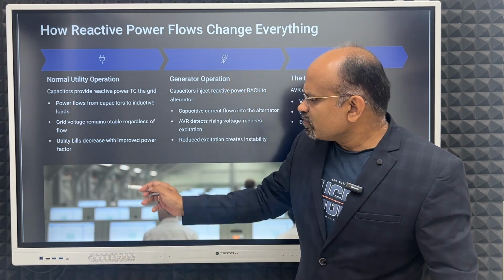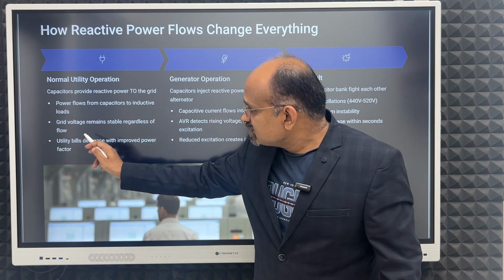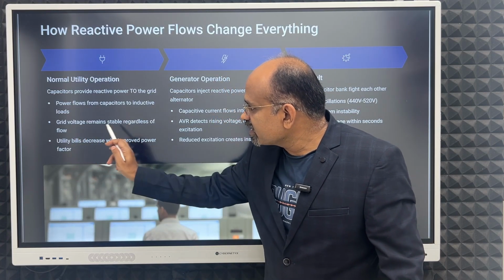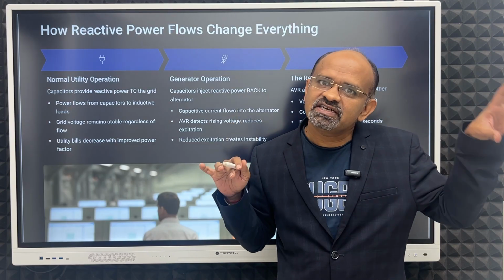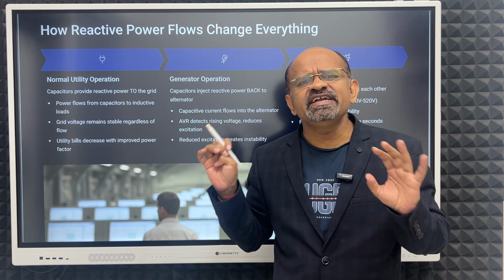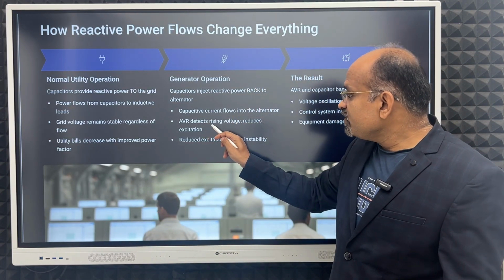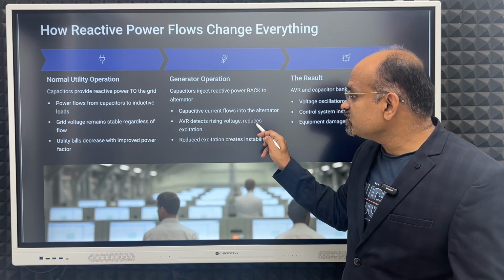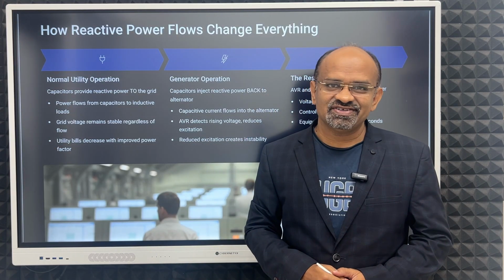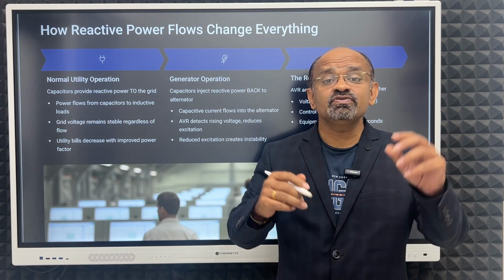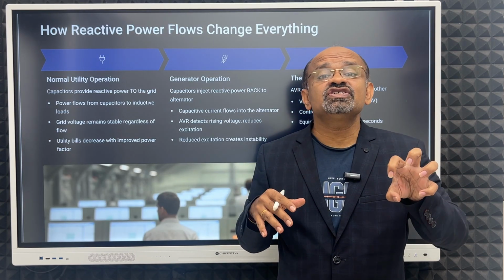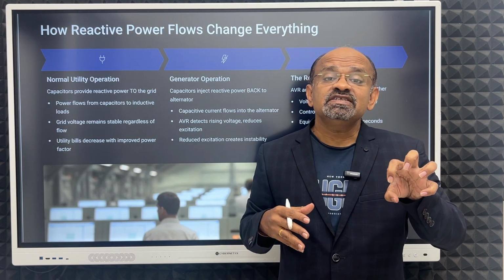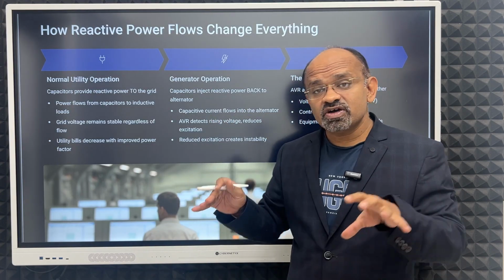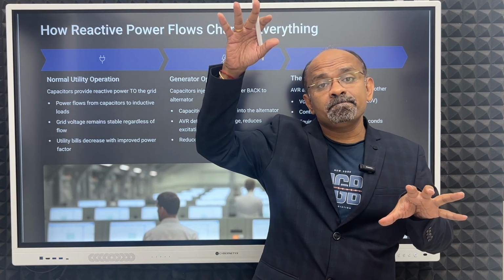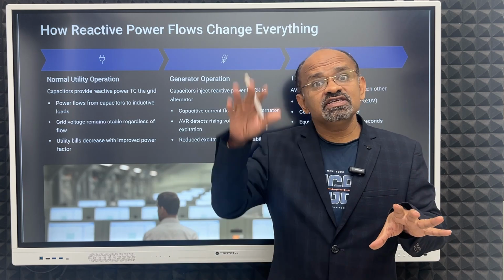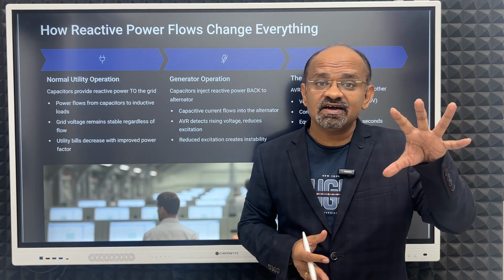Now, grid voltage remains stable regardless of flow, because inductors and capacitors are both there, maintaining the voltage. Here, the AVR detects rising voltage and reduces excitation. What happens then? Your voltage level will go down because of the capacitor, voltage goes up, and the AVR senses that voltage is up, so why should it increase excitation?